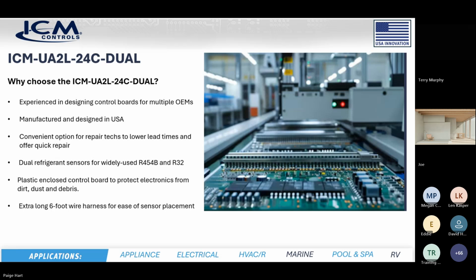So it makes it a very convenient option for people to cover a wide variety of different applications. Its plastic enclosed control board protects the electronics from dust, dirt, and debris. So we have a nice enclosure so it doesn't get moisture, dirt, or debris in there that can damage the board. And it comes with an extra long 6-foot wire harness for the sensor placement. Because we don't know exactly where you're going to have to place a sensor, and don't forget the size of the board. When you mount the board in there, you have another 3 or 4 inches to worry about. So we give you an extra long cord so that you should be able to locate it wherever you need to mitigate your leaks.